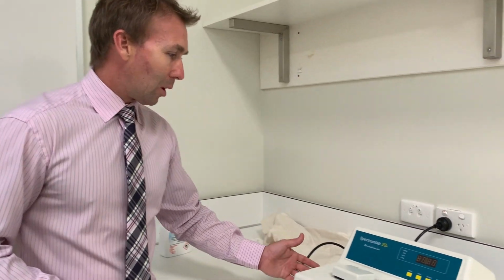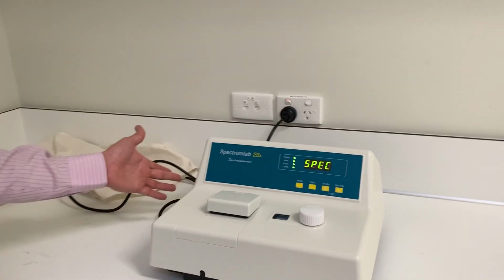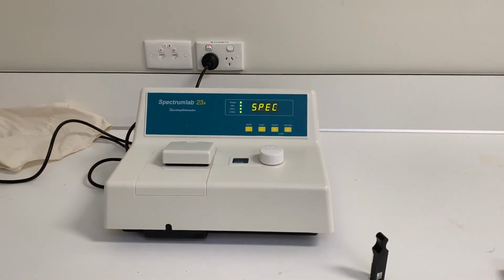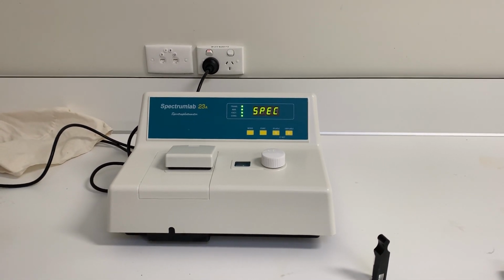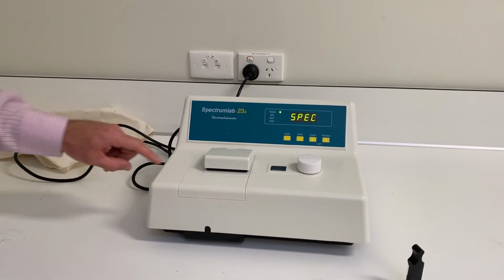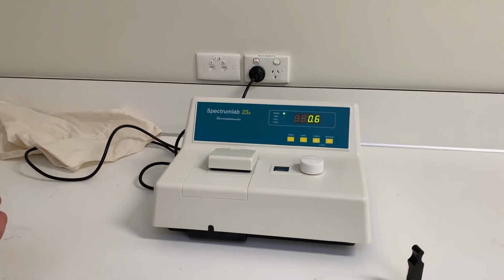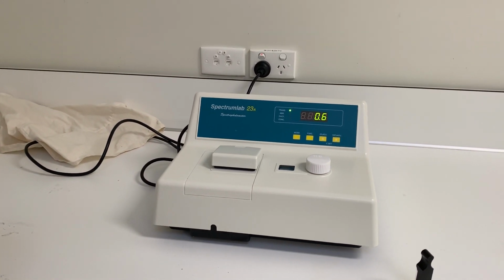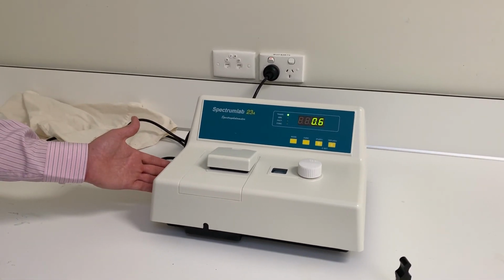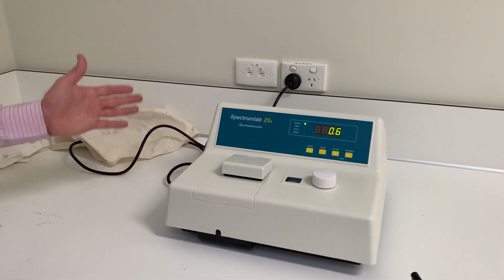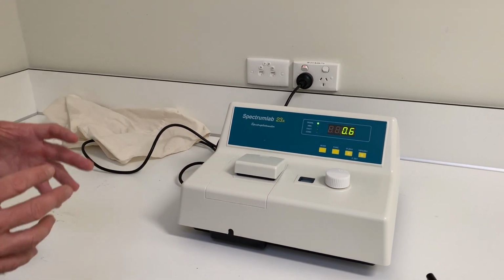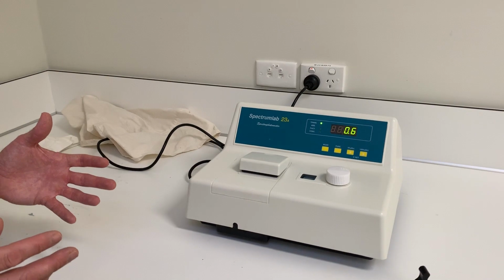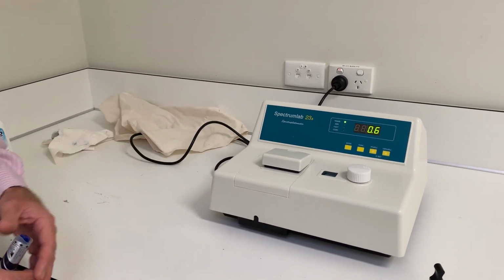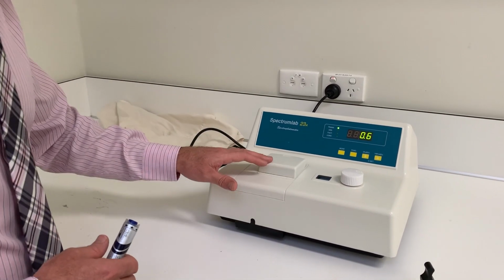Right, first thing you want to do when you come in is turn on your machine on the side there, and it will start to warm up. Now there's a monochromatic light source inside here, and that light source also needs to warm up, so the first thing you should do before you start setting up is just turn it on, because after 20 minutes or so you'll get much more accurate readings than if you just start right from the word go. So turn it on first.